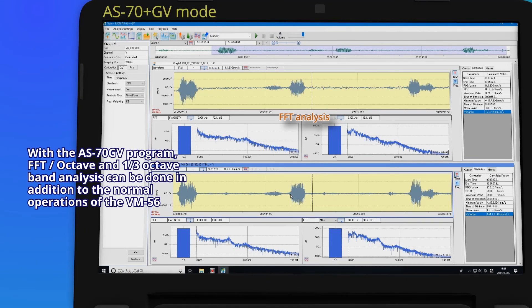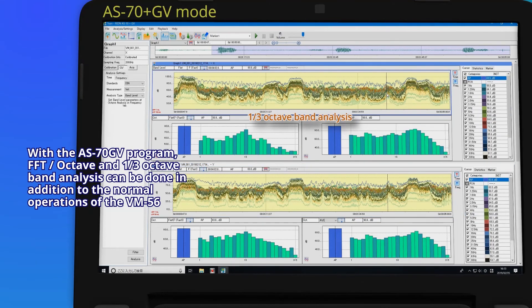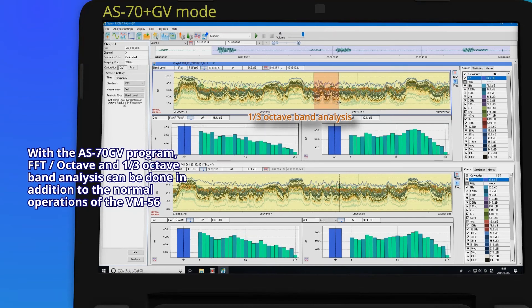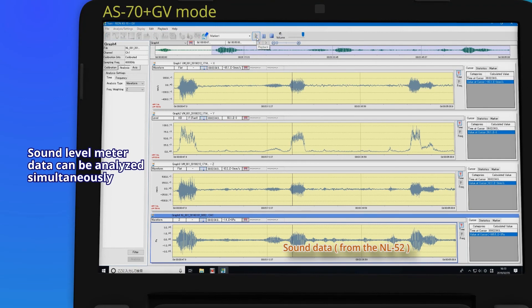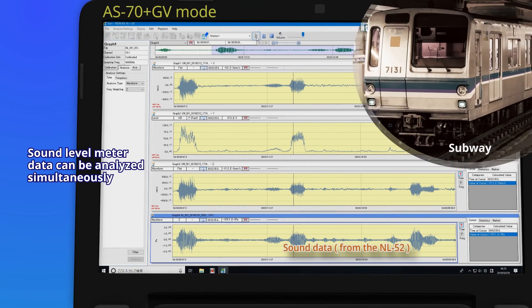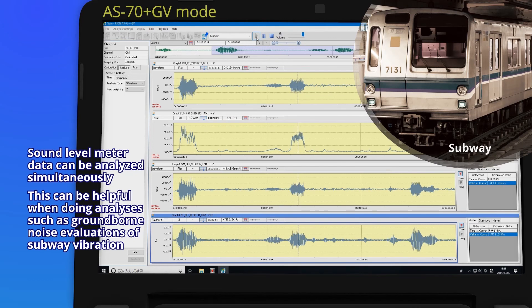With the AS-70GV program, FFT octave and one-third octave band analysis can be done in addition to the normal operations of the VM56. Sound level meter data can be analyzed simultaneously. This can be helpful when doing analyses such as ground-borne noise evaluations of subway vibration.